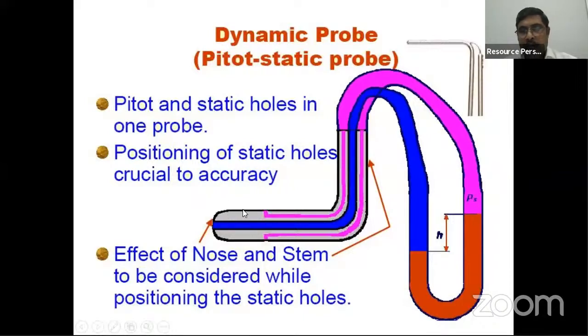So in that case, the probe will not measure the correct value of static pressure, because the static pressure experienced by the probe will be lesser than the true value because of this effect. Now the static hole, this hole is close to the stem. Basically, the stem stagnates the flow. It will stagnate the flow because of the stagnation effect. What will happen?